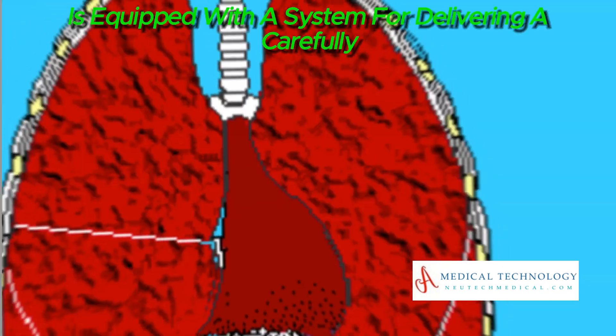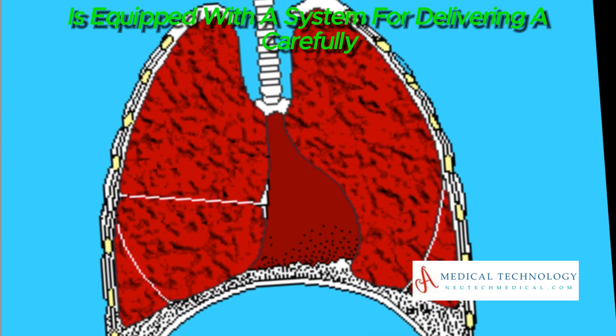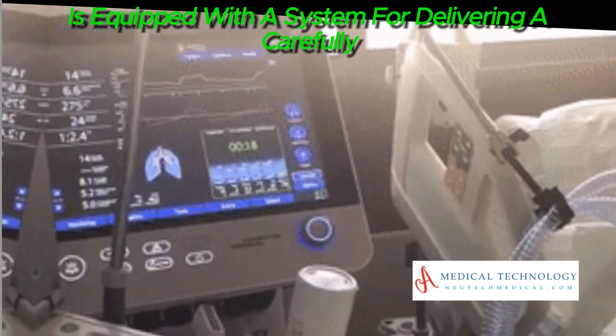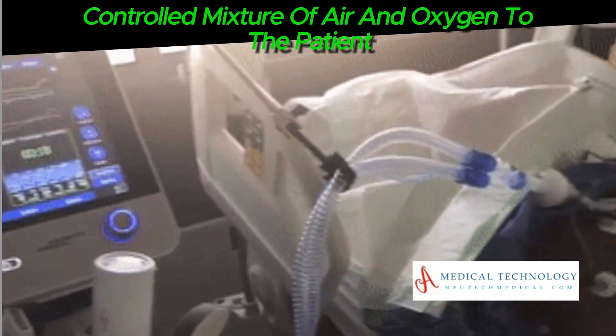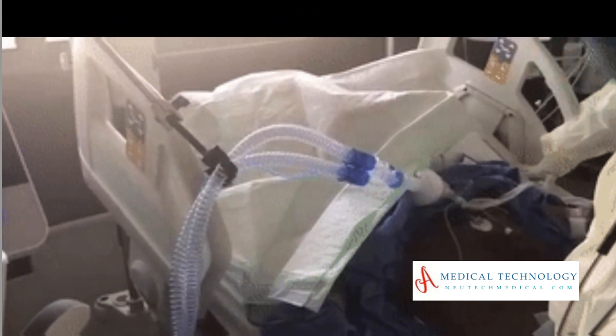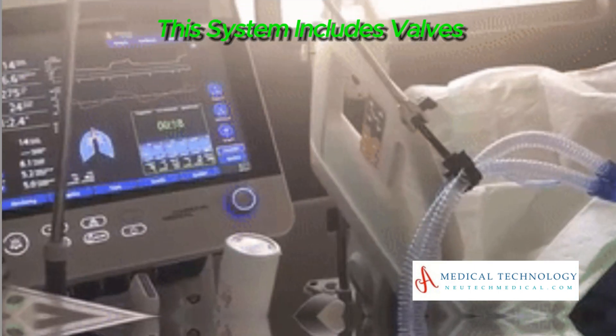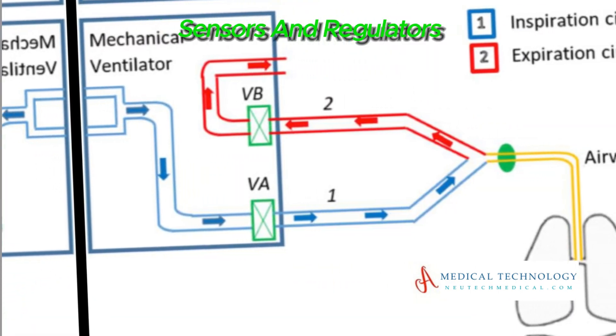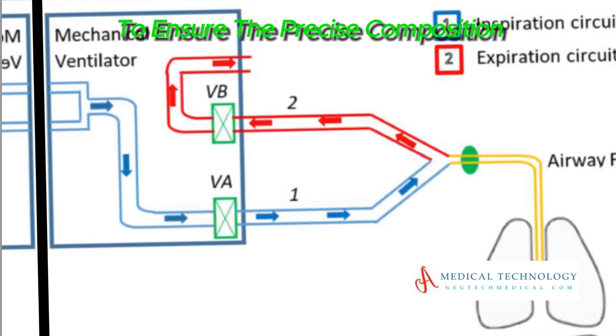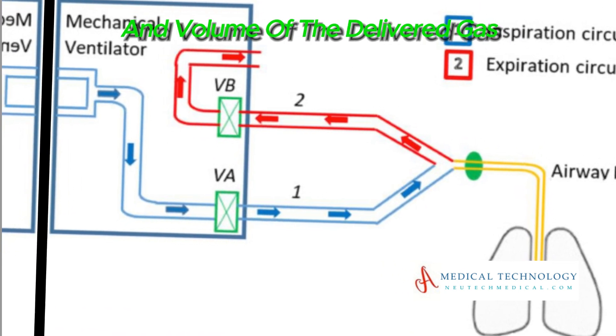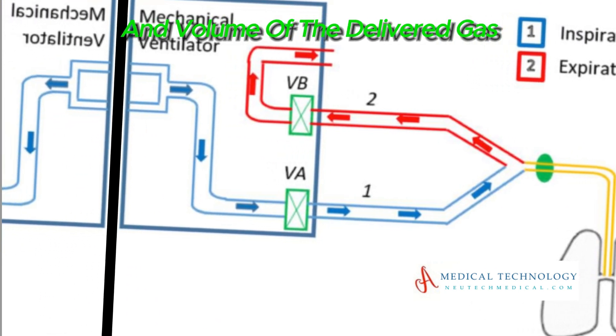The ventilator is equipped with a system for delivering a carefully controlled mixture of air and oxygen to the patient. This system includes valves, sensors, and regulators to ensure the precise composition and volume of the delivered gas.